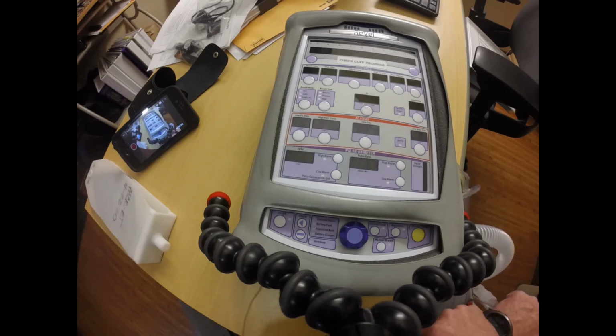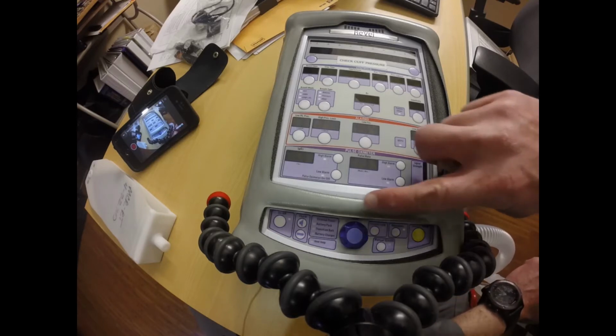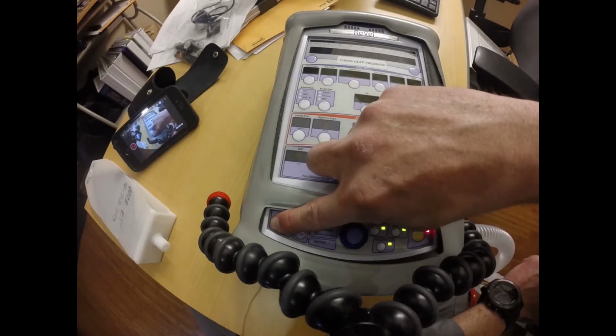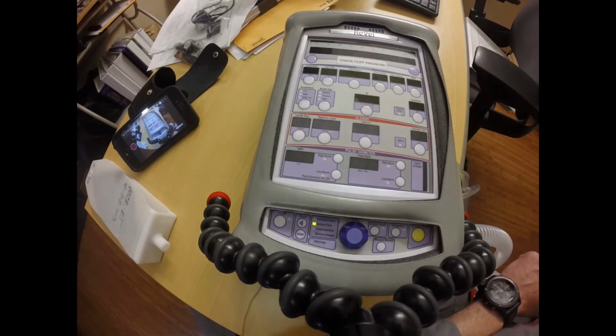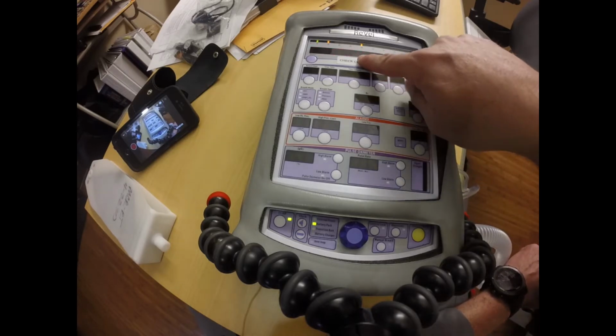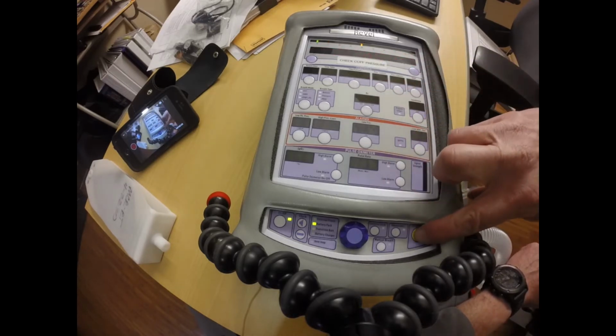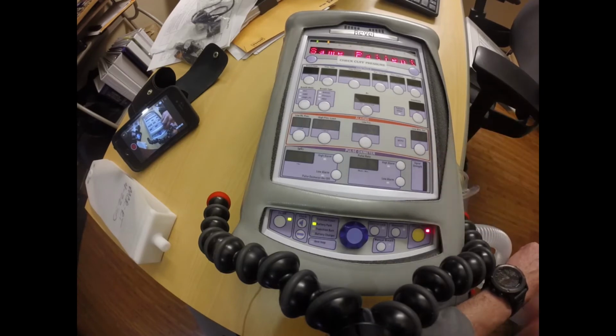So my circuit is now applied, and at every shift we like to make sure that the circuit is intact and working properly before we do a patient transport. So I'm going to go ahead and do a circuit check at this point. To do that, I'm going to turn the ventilator on. It's going to give me a couple of alarms here real quick, so external power loss. I'm going to silence that, push it twice to get out of it.